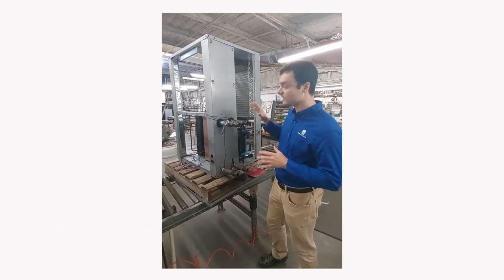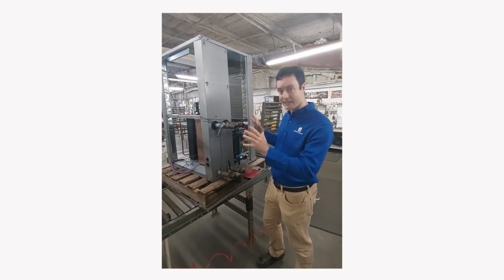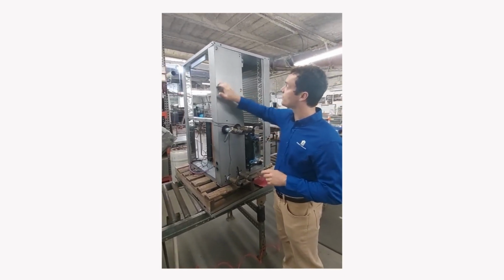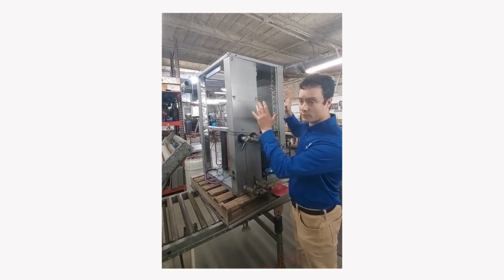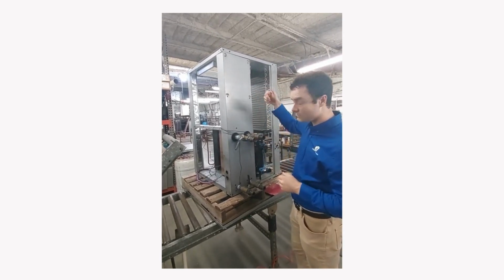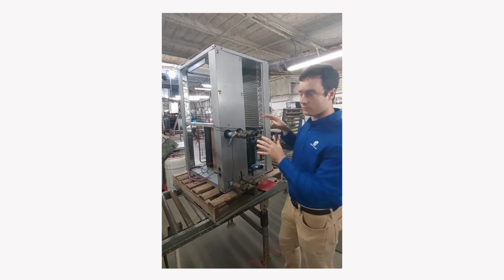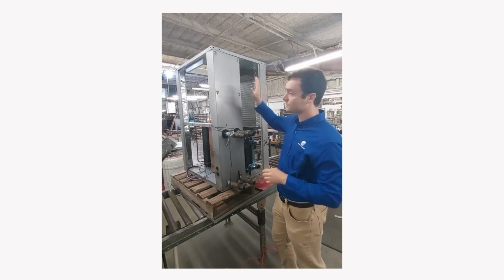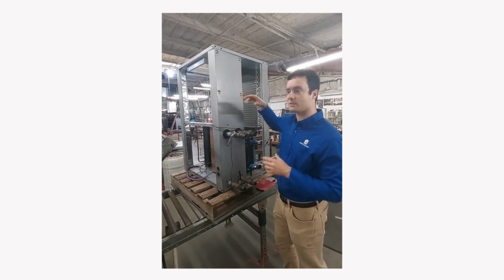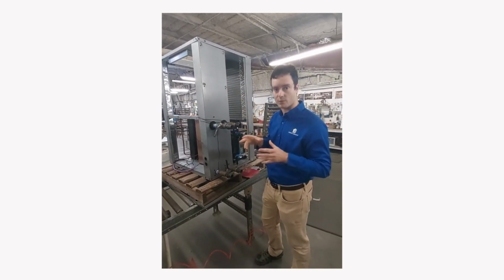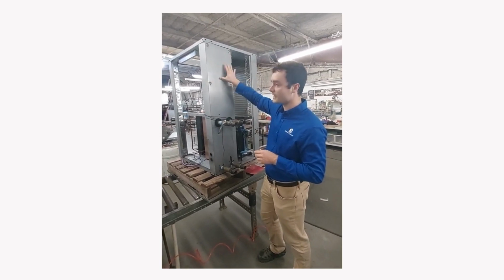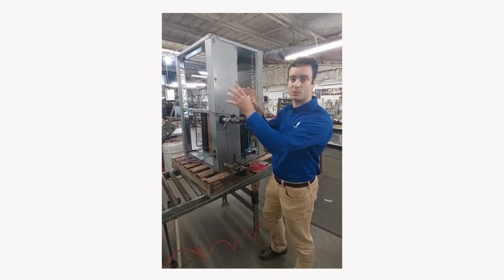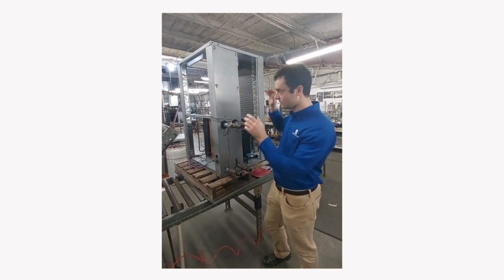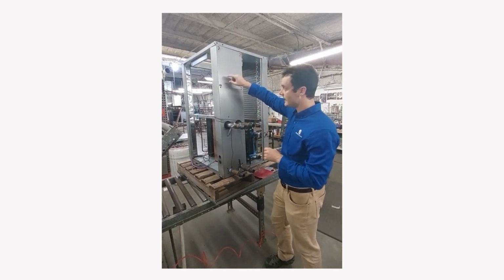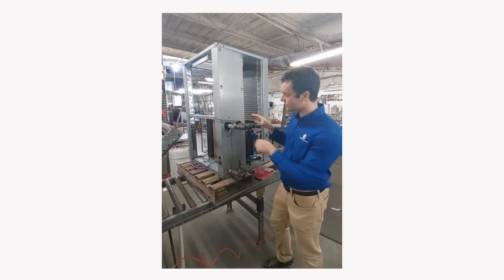So this unit itself is designed to be very packaged together. You can see these 4 holes right here. That is for the ground loop pump. And all the controls and wiring is done right into the panel. So this will control variable speed pumps. It'll provide the exact amount of water required. Because it's all pre-packaged, you don't have to mount this pump to a wall or somewhere else. You bring your pumps right into here. And then from here, these are the 2 ground loops.